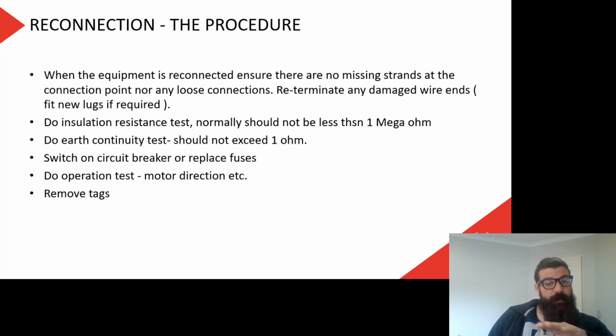We need to do an insulation resistance test, and normally the reading should be more than 1 mega ohm, so 1 million ohms. Until we get more into some of the specialist testing, the relevance of insulation testing perhaps won't mean much to you, but we're just testing that there's no leakage between one conductor and another, which I have talked about before. When it says normally 1 mega ohm, we do have situations where it might be less, particularly with water heating appliances, so hot water cylinders and stuff like that. You can get readings that are less than 1 mega ohm. So in that case, with a water heating appliance, the minimum reading is 10,000.